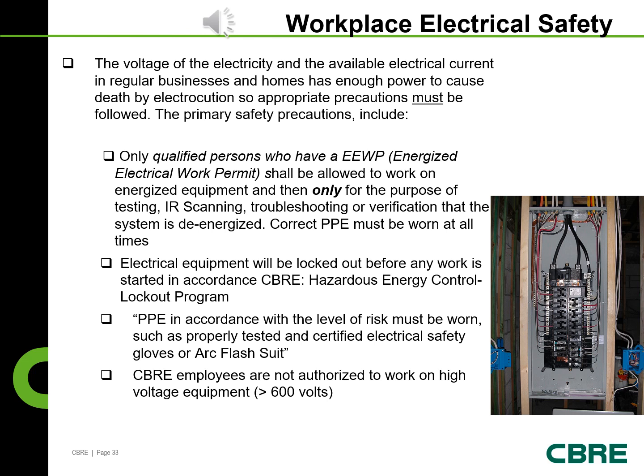Workplace electrical safety. The voltage of the electricity and available electrical current in regular business and homes has enough power to cause death by electrocution, so appropriate precautions must be followed. The primary safety precautions include: only qualified persons who have an EEWP, energized electrical work permit, shall be allowed to work on energized electrical equipment, and then only for the purpose of testing, IR scanning, troubleshooting, or verification that the system is de-energized. Correct PPE must be worn at all times.